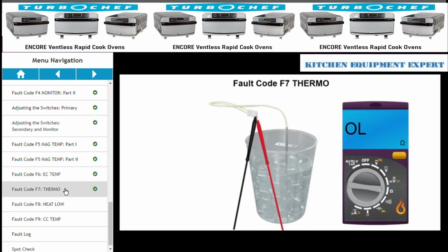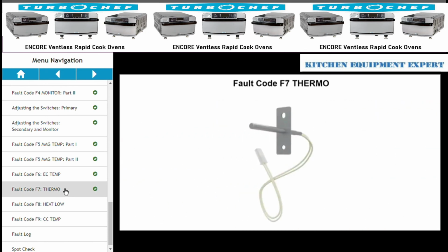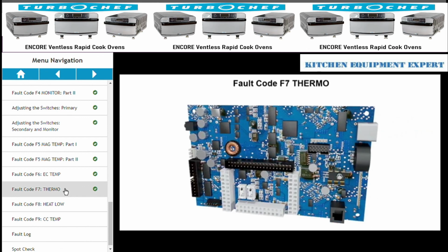If the F7 fault is intermittent but the RTDs test okay, the top RTD most likely has an internal breakdown and should be replaced. If the problem persists, the control board should be replaced.